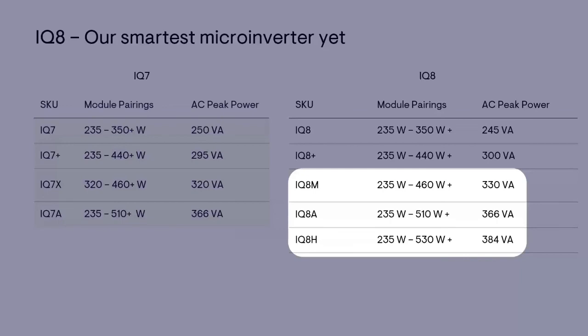I'll try to get through the last 5 or 10 fairly quickly. So, once the generator update comes, will there be a maximum size for the generator? The maximum breaker is 80 amps with a system controller too, so that's 64 amps of current. You can install a larger generator that's by itself capable of more than 64 amps, but it's going to be limited to 64 amps by the Enphase system. That's pretty important to understand.